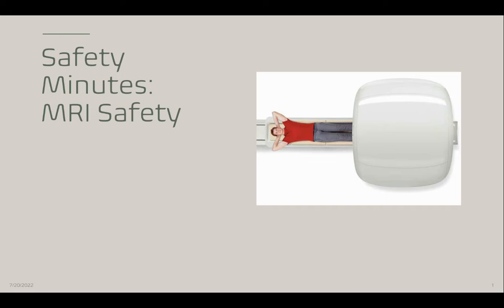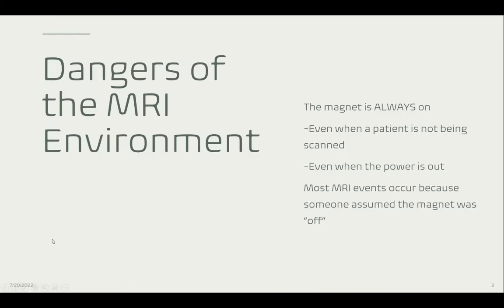This Safety Minutes video is brought to you by the Safety Coaches. What do you need to know about MRI safety? Both clinical and non-clinical personnel need to be aware of the dangers posed by the MRI unit. The magnet is always on, even when a patient is not being scanned and even if the power is out. Most MRI events occur because someone assumed that the magnet was off.